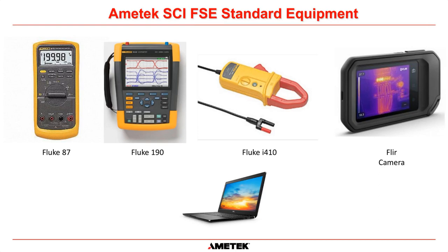So here are the tools that all of our field service engineers take out to site to perform the PM services on an AMETEK UPS. So we take out a Fluke 87. Every single one of our field service guys has a Fluke 190 oscilloscope, a Fluke I410 amp clamp, some form of FLIR infrared thermal imaging, whether it's a FLIR C1 or the new FLIR Edge, a laptop, and now every single one of our field service engineers also has an iPad because we're doing all of our reports using an offline app on an iPad. And we can download all of the pictures from the cameras and the oscilloscopes into that iPad. And get a very, very in-depth report at the end of it.